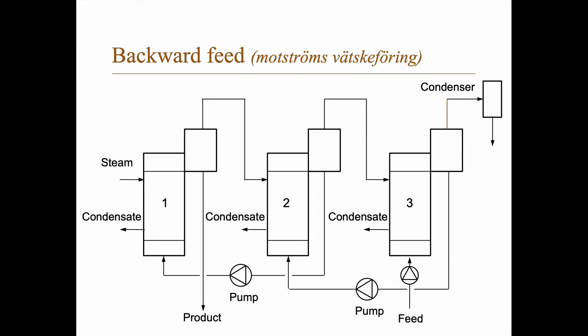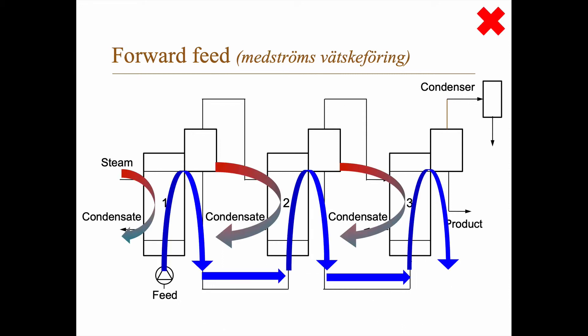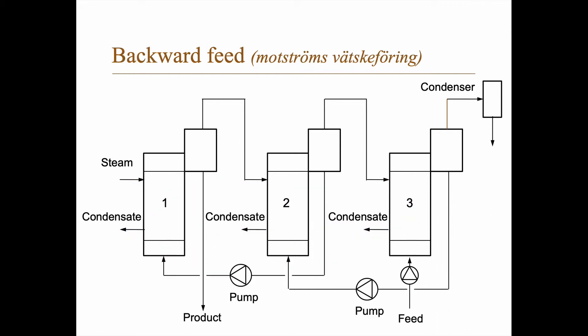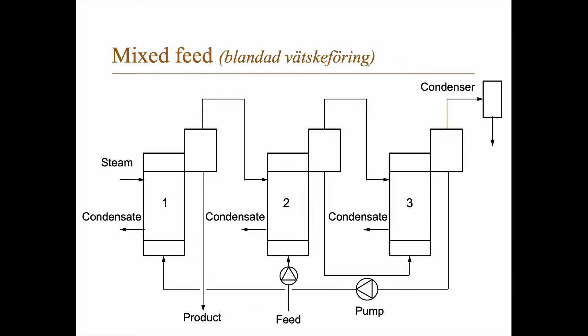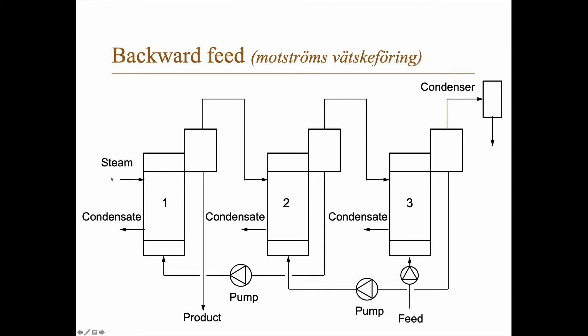Backward feed is the opposite. With forward feed, you need to pump the feed into the first evaporator, but then the pressure is lower in evaporators two and three, so the feed may flow without pumping due to the pressure difference. In backward feed, however, you put the feed into the last evaporator, so although the steam still goes in the same direction, the feed goes in the opposite direction — from low pressure to higher and higher pressure. That means you definitely need a pump between each evaporator.